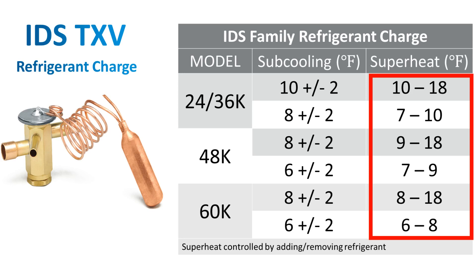If you find your superheat is greater than 18 degrees, you need to add refrigerant to bring the superheat in range. If your superheat is less than 6 degrees, you would do the opposite and remove refrigerant to warm up your suction line.